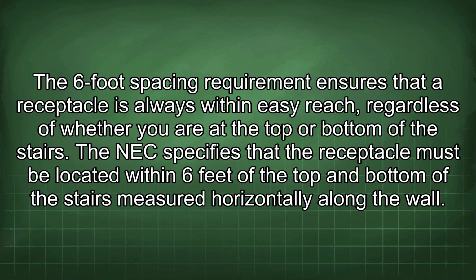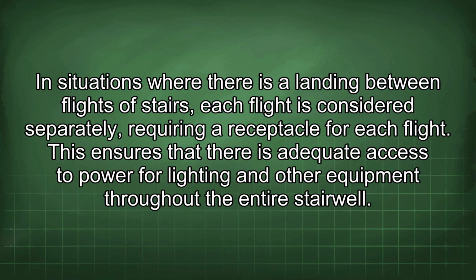The NEC specifies that the receptacle must be located within 6 feet of the top and bottom of the stairs, measured horizontally along the wall. In situations where there is a landing between flights of stairs, each flight is considered separately, requiring a receptacle for each flight. This ensures that there is adequate access to power for lighting and other equipment throughout the entire stairwell.